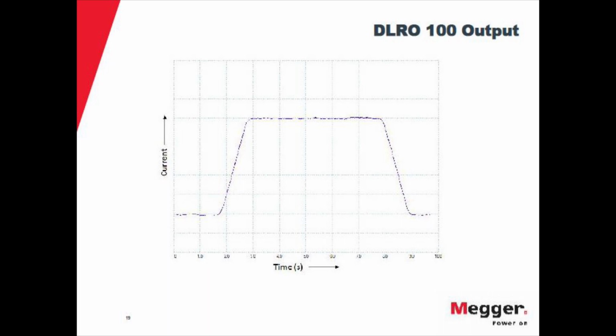I was mentioning that you need a very smooth curve, and you need an easy ramp. This is an actual oscilloscope screenshot of the signal from this instrument, and you see that you have a very smooth, very well rectified signal output. And this ramp you can adjust. Here it's about a 5-second ramp, but it can be adjusted up to a 15-second ramp. So it's going to be a very smooth ramp. It won't affect any protection system in the breaker or element that you are testing. That is in relation to low resistance measurement.